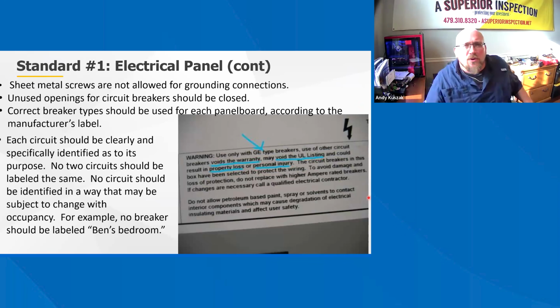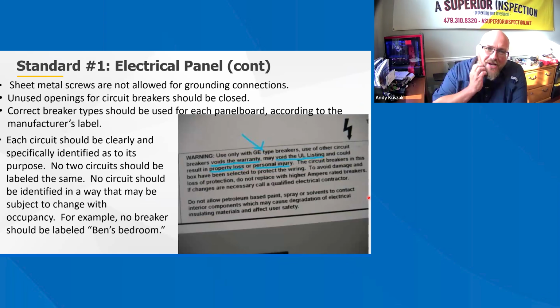Okay, standard number 1, electrical panels. So remember, sheet metal screws are not allowed for grounding connections. Again, kind of one of those flipper deals. You've got to keep an eye out to make sure that the proper components are installed at the correct locations. Unused openings for circuit breakers should be closed with approved panel covers or inserts.